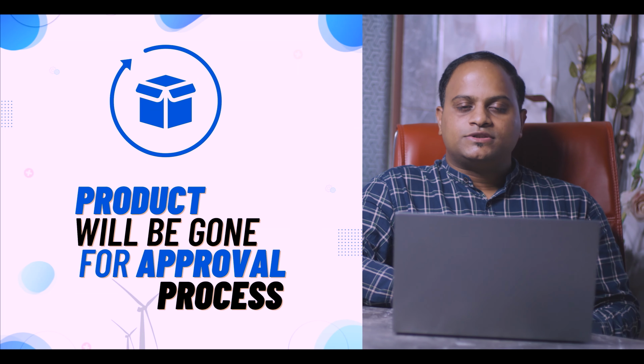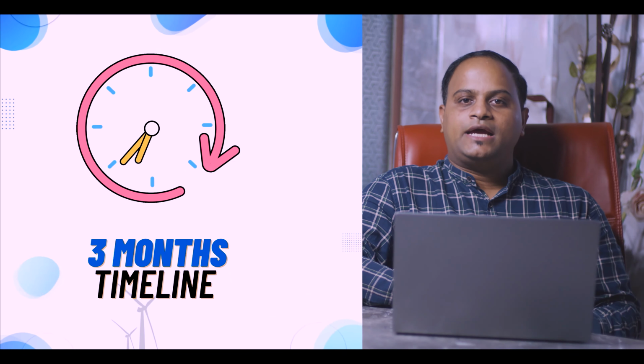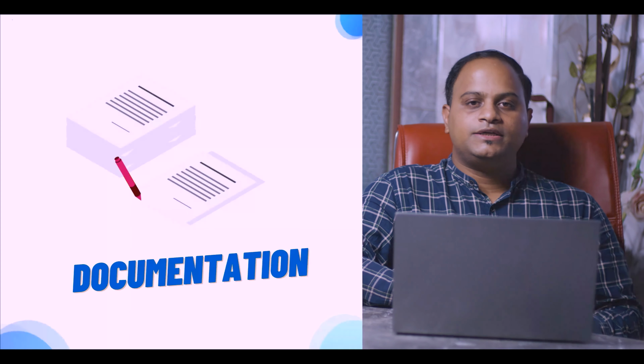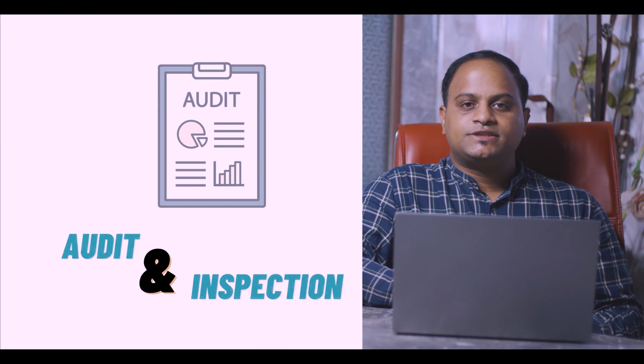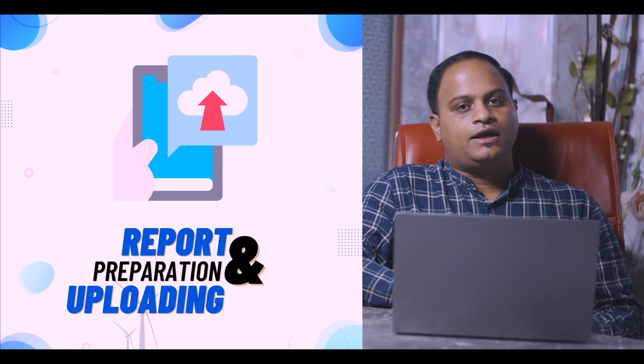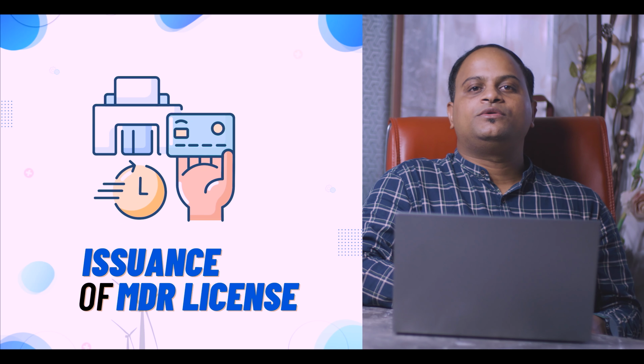After that, your product goes for the approval process, which takes a 3 month timeline. This timeline covers the whole process: documentation, review, audit inspection, and report preparation and uploading, and finally you get the approval as per the required category. So that is all you need to know about the approval and licensing process for medical devices as per MDR 17 rules, regulations and guidelines.